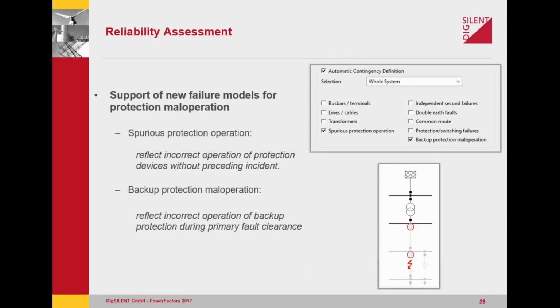In PowerFactory 2017, 2 new failure modes for reliability analysis have been added: spurious protection operation and backup protection maloperation. Spurious protection operation models protection maloperation which results in the opening of an event of a breaker without any preceding short circuit. And backup protection maloperation is the incorrect operation of backup protection whilst the fault is being cleared via the primary protection, for a range of reasons such as poor protection adjustment or measurement errors. For both these types of failure, probabilities are provided by the user via the switch object.